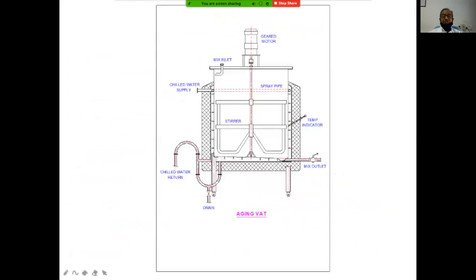Now, how does the ageing vat look? The ageing vat is a simple vessel with a stirrer. There is a spray system or the DX system here in the jacket, and the motor is stirring at a slow speed so that a uniform temperature is maintained. In case we supply chill water, it supplies the jacket, is sprayed on the outer wall of the inner tank, and returns back to the plant.